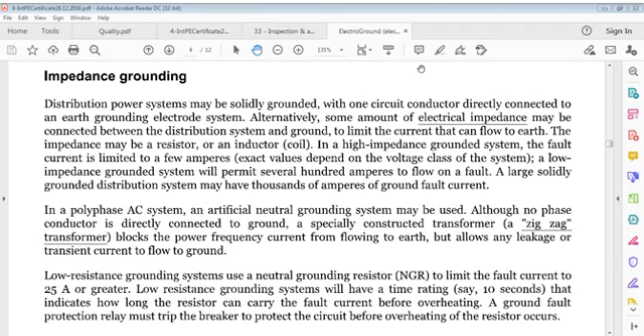Alternatively, some amount of electrical impedance may be connected between the distribution system and ground to limit current that can flow to earth. Impedance may be a resistor or an inductor coil. In a high impedance ground system, fault current is limited to a few amperes. Exact values depend on the voltage class of the system. A low impedance grounded system shall permit several hundred amperes to flow on a fault. A large solidly grounded distribution system may have thousands of amperes of ground fault current.